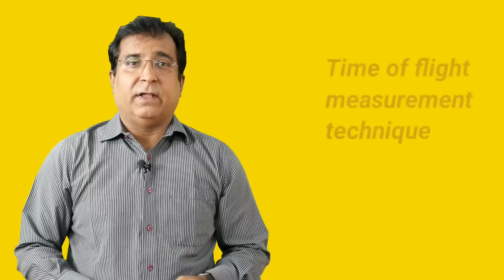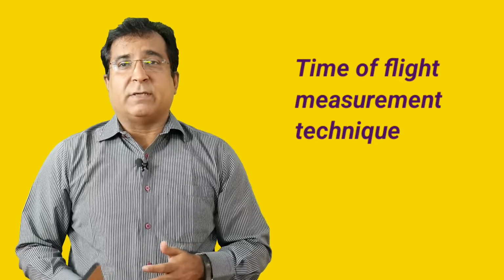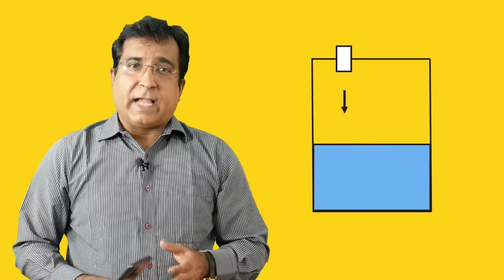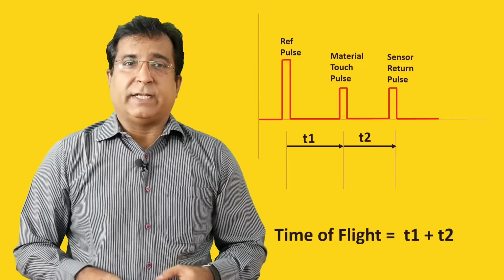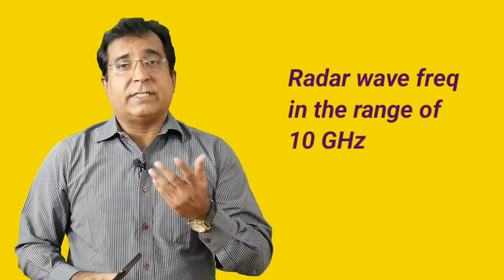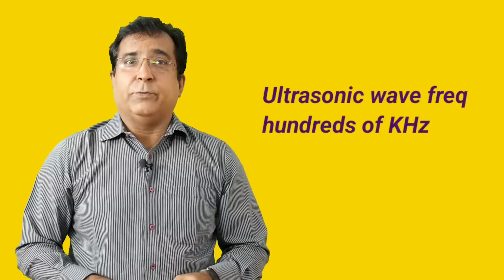Let's start with how they operate so that we can get a fair idea of selection. Both techniques use the time of flight measurement principle. It is the time taken by a wave to hit the target material and reach back to the sensor. Radar makes use of electromagnetic waves, which lie in the X-band range near 10 GHz, and these waves travel toward the target material at almost the speed of light. Ultrasonic makes use of sound waves at a frequency of some hundreds of kilohertz, which is higher than the human ear can respond to. That's why these waves are not audible to the human ear, and they are emitted in the form of bursts of sound waves in very rapid succession.